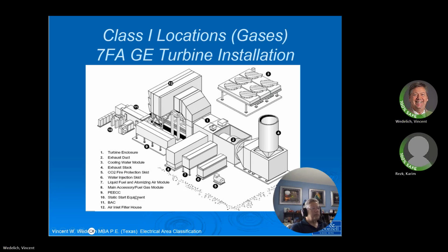So my point is, on the one where it says turbine enclosure, if you have a turbine enclosure or a generator somewhere in there, this actually can be filled with hydrogen, because it keeps that generator cool. So you've got to watch for that as well. But definitely, I would say without a doubt, seven and eight are classified for sure.